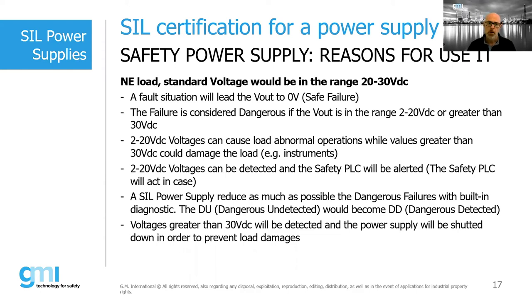Plus, a fault transistor alerts the PLC system, which can act as per SIL specification. Even in case of a separate power supply output overvoltage condition, the internal diagnostic activates the redundant protection system for limiting the output voltage, which brings the latter to 0 volt. This means a safe fault condition.